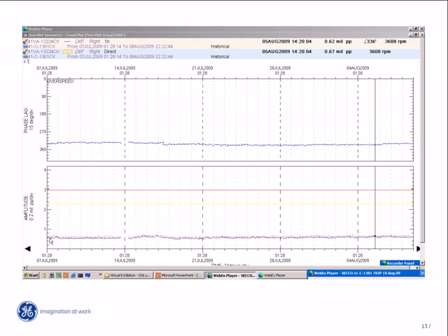Let's take another look at this vibration to see if we could see any early indication that this event might have given us some forewarning. Looking again at the overall vibration since July 7th, we can really see that the vibration was in fact very steady. So there was no early warning from this vibration. In fact, by looking at vibration, we only got 2 minutes between seeing that slight increase until the machine tripped.